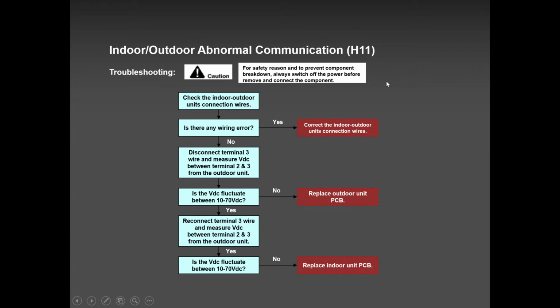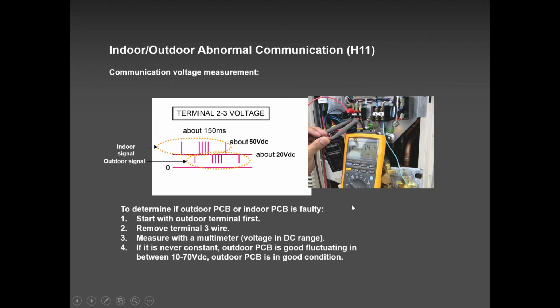Okay, and this is how you follow up. What you do is very simple. Go to the outdoor unit and remove the number 3 wire. The number 1, 2, and 3 that goes to the indoor unit. Just remove number 3 wire. Power the unit on. So obviously power the unit off. Remove number 3 wire. Keep it hanging. Power the unit on. Measure the voltage using that meter.